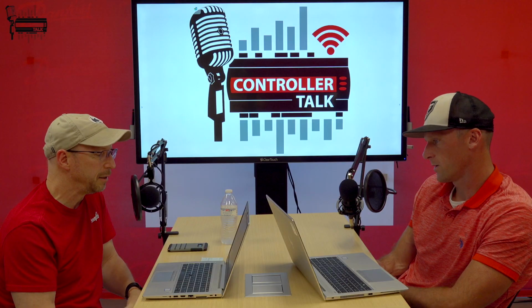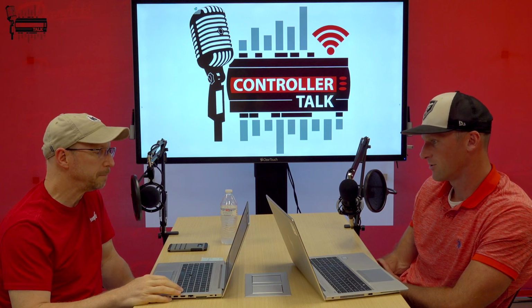So in terms of the matrix of pack controllers, our little guy here is the PC 351. It can control one suction group and one condenser, with up to 4 compressors, one of them being variable speed, and the condenser can have 4 stages or speed control. Total inputs and outputs come to 20. Nice little controller for a condensing unit or tandem setup — maybe not supermarket, maybe not part of the main rack, but it fills a gap that our larger stuff would be overkill for.